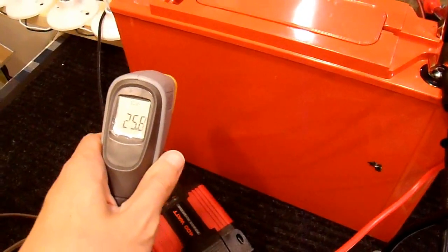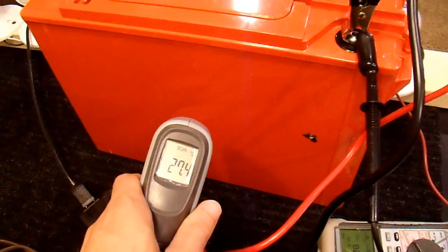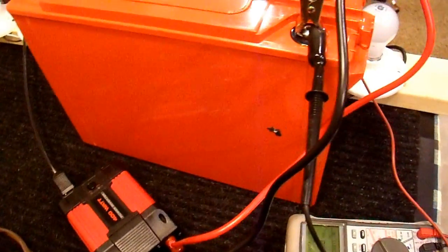Now in terms of temperature on the battery you can't see me feel the battery in terms of what temperature I feel with my hands. So I'm gonna use this meter so you can actually see. Now the whole battery on both sides is about 26 degrees Celsius. But this one cell here is about 28 degrees Celsius.